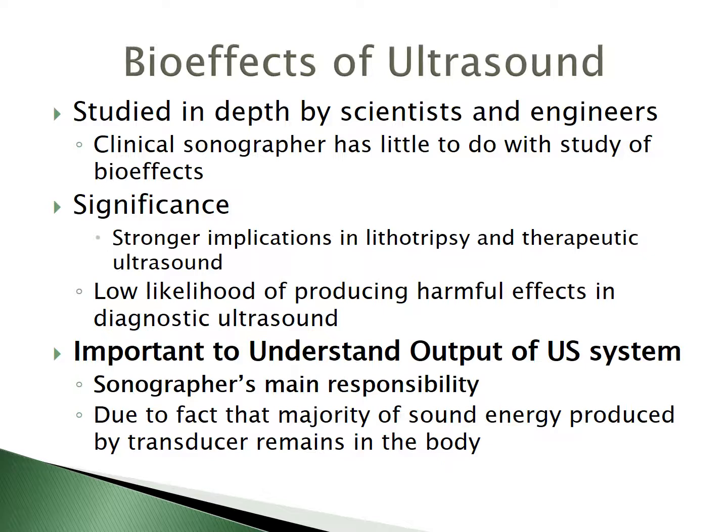But we're still using these on babies, we're still using these on human tissue, so we need to be able to monitor and see what could happen if we actually produced bioeffects. So it's very important as a sonographer to understand the output of the ultrasound system. We have talked about ALARA in the past, and it is also important to know how certain settings are going to affect the MI and TI using the power system, and we'll get into that a little more in this lecture and how it relates to bioeffects.